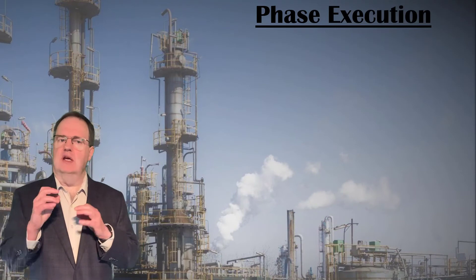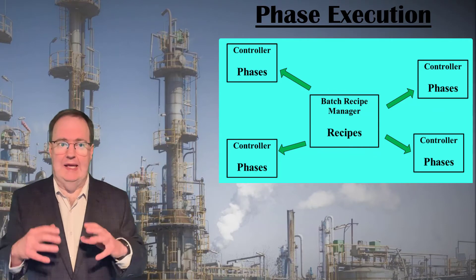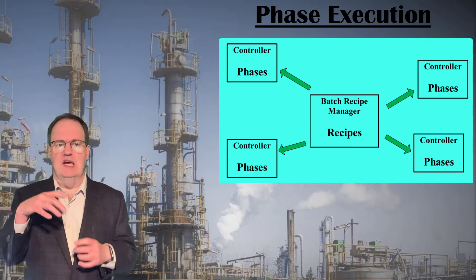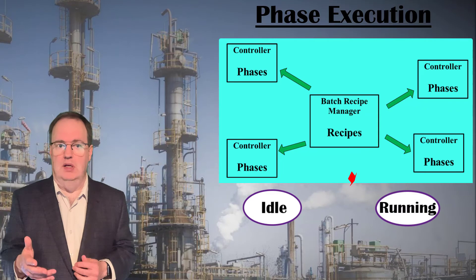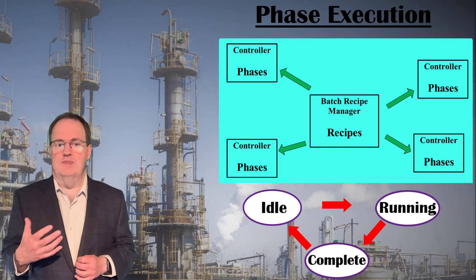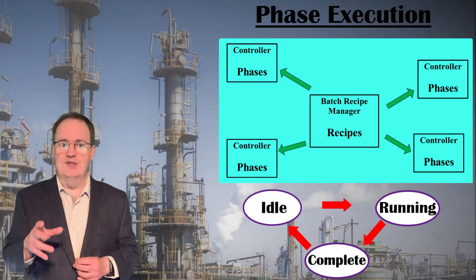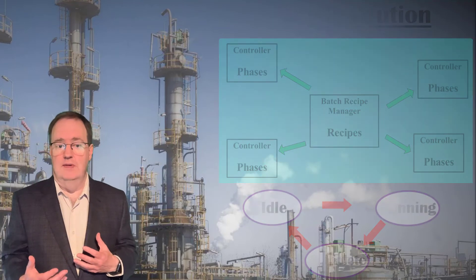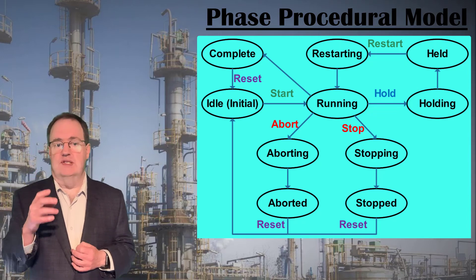When a unit recipe sends a command for a phase to execute, unit recipes often reside in a batch recipe manager application on a server for the whole plant. The unit-specific phases, on the other hand, reside on high-speed controllers that are also cycling control loops and interlocks several times a second. A phase sits idle until called to action by a recipe, then ideally runs to completion. But as with all things in a process plant, we have to plan for when things go wrong. If a potential hazard is detected, interlocks or an operator might pause or stop an entire batch recipe or just a specific phase. The S88 standard has a phase procedural model that addresses this, which all control system manufacturers support.